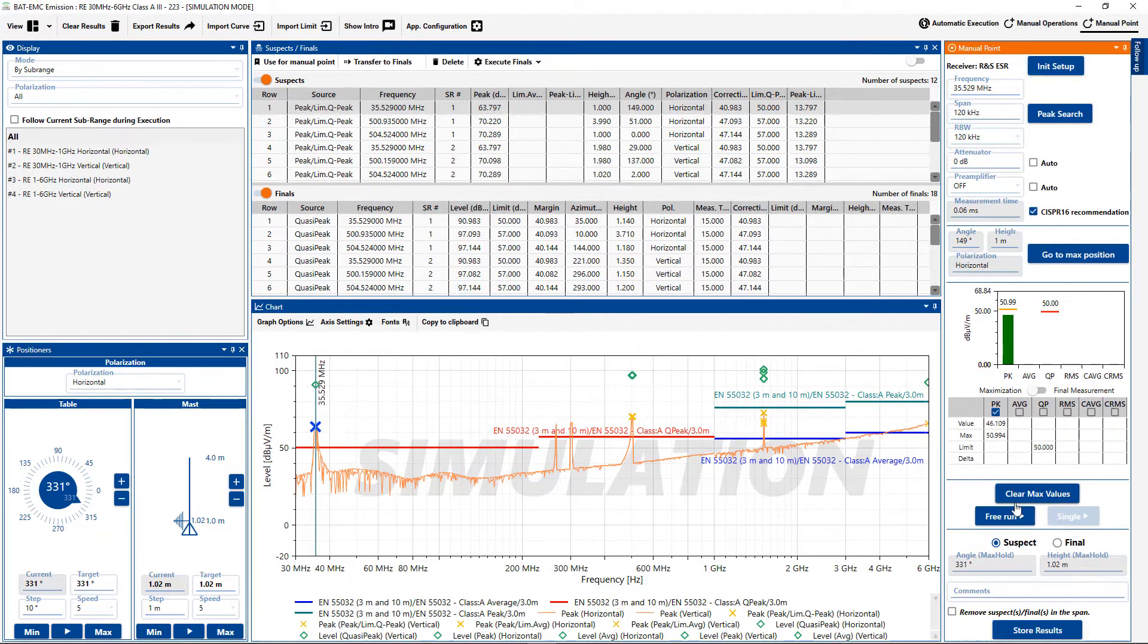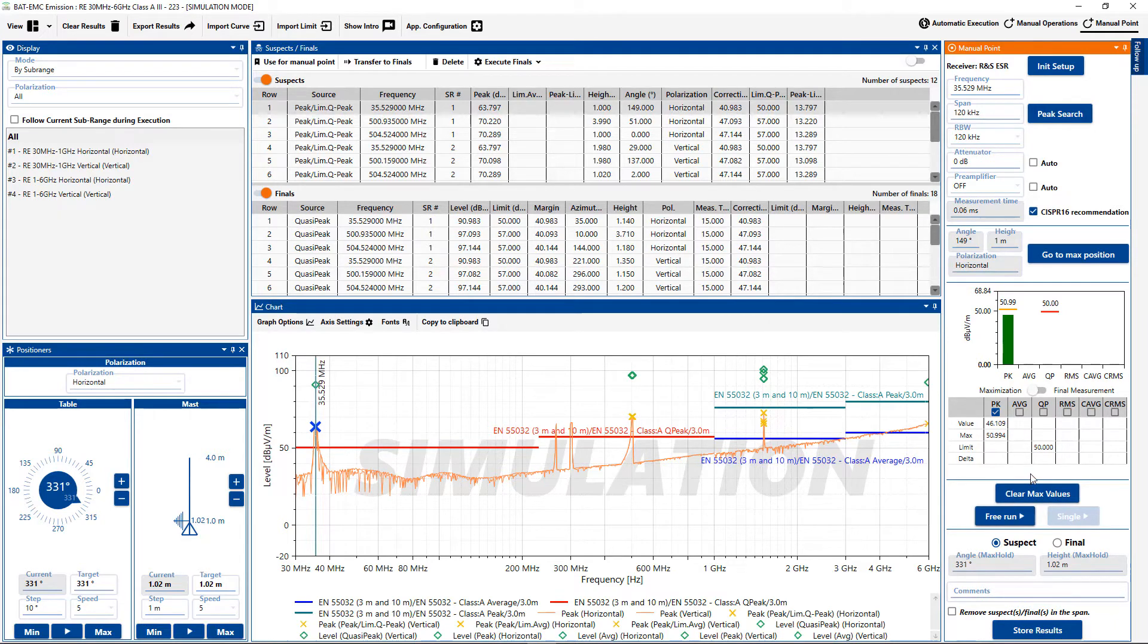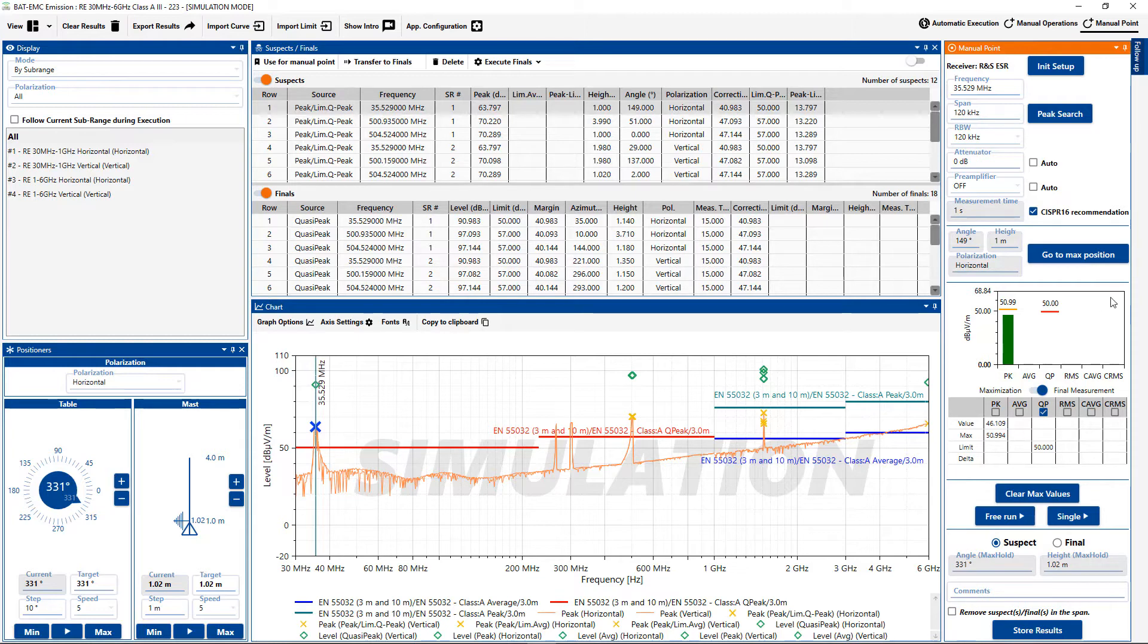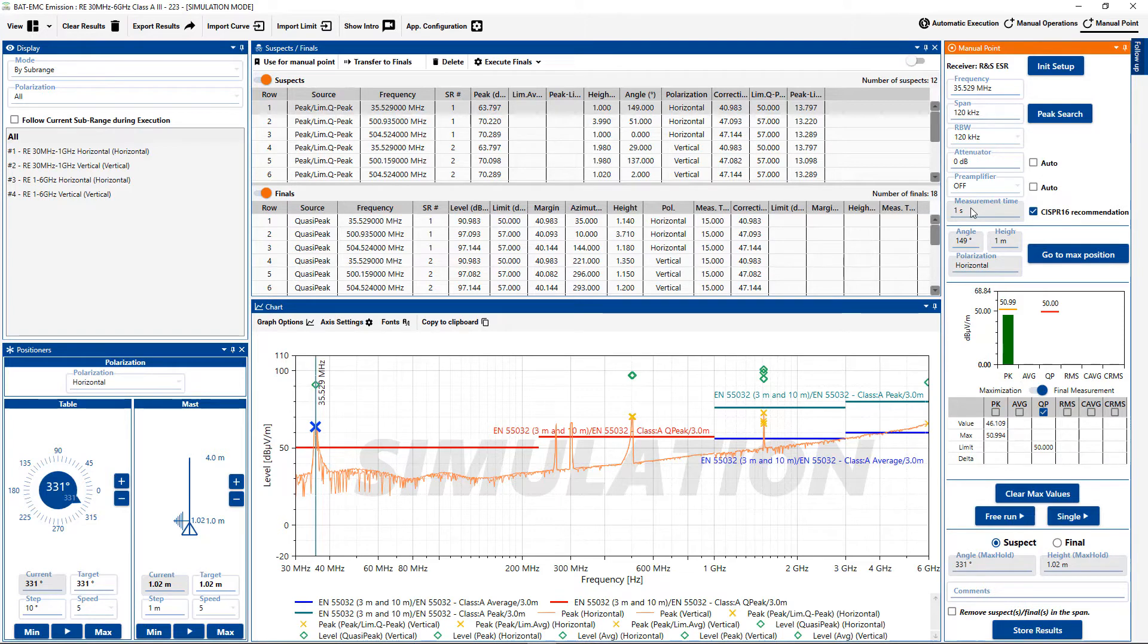I can stop that measurement, and now we're going to do a final measurement. Because we're in a range below 1 GHz, we're going to use the quasi-peak detector for that. And as you can see, because I changed to the quasi-peak detector, the measurement time came up to 1 second. It could be set to a higher amount, for example, if the peak was unsteady.